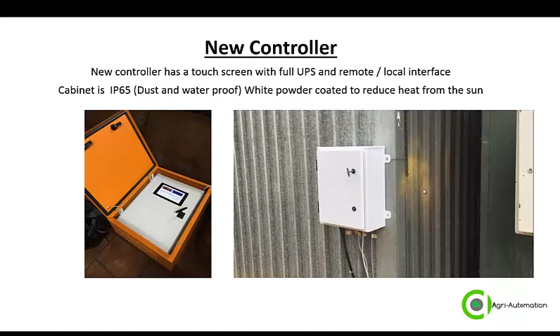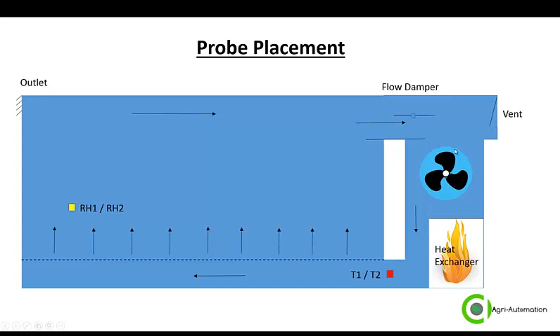We've made the cabinet white so that the sun doesn't play a major role with the electronics inside the cabinet. And this is where we've decided to place the probes. The temperature probe T1 and T2 is basically placed here, and then we've got one relative humidity probe over here. We open the damper all the way, and we use a VSD to control the speed of the fan.